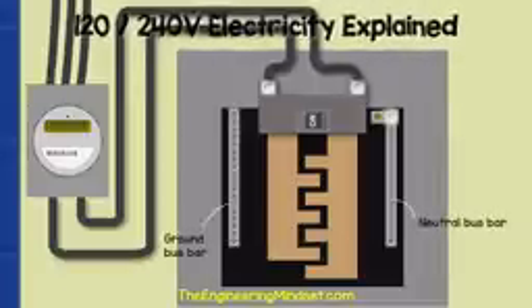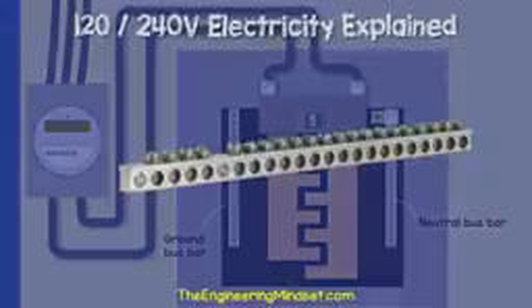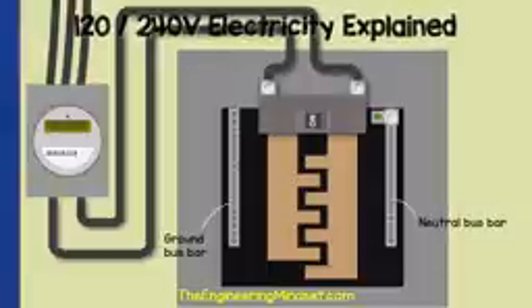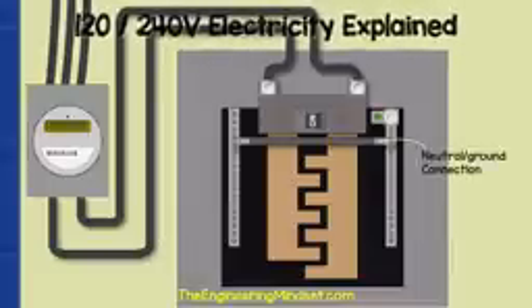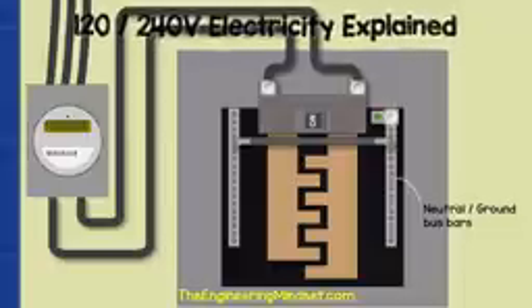Inside the panel, we also have a neutral and ground bus bar. This is basically a strip of metal with lots of holes and screws in it. The neutral and ground wires will sit in the holes and the screws will lock them in place. In this example, we have a block on either side of the panel. As this is a main panel, the 2 bus bars can be joined together, so we have a connector bar between them. That way we have a shared neutral ground bus bar. Sub-panels must have their bars separated, but that's a topic for a separate video.